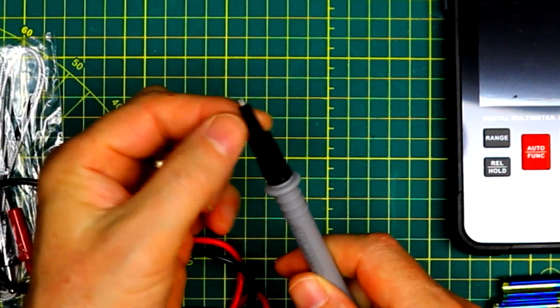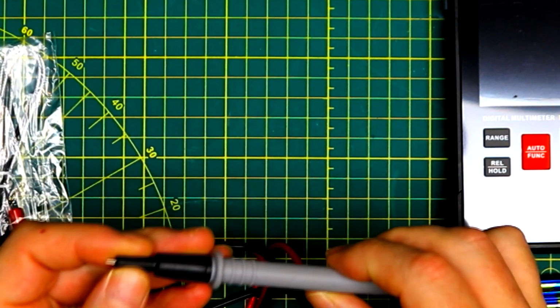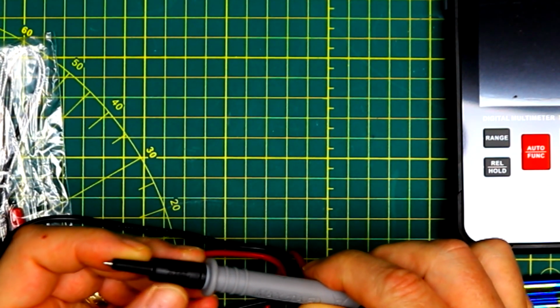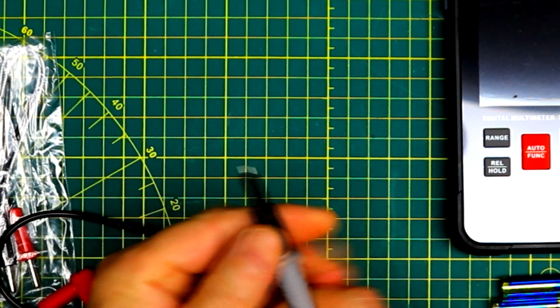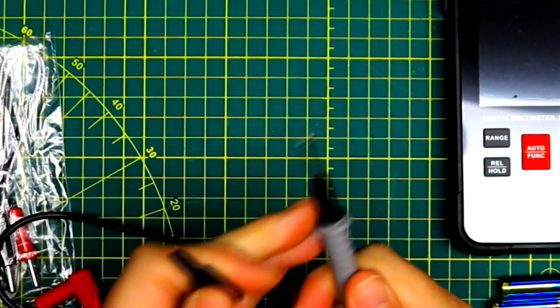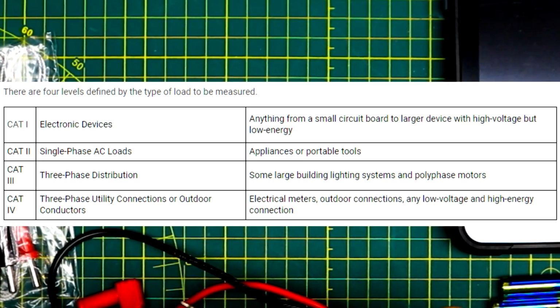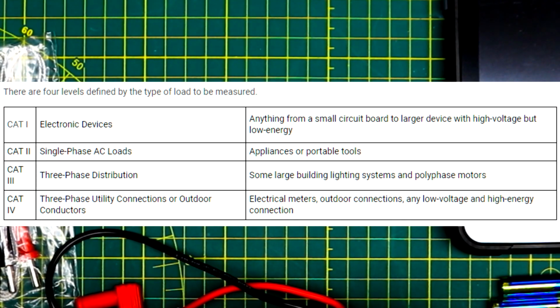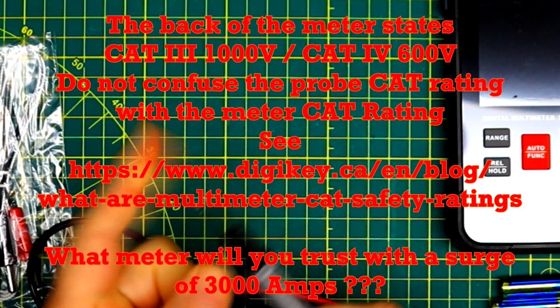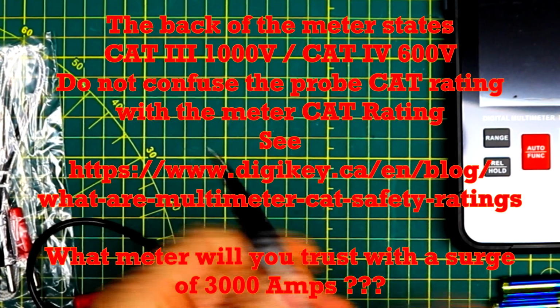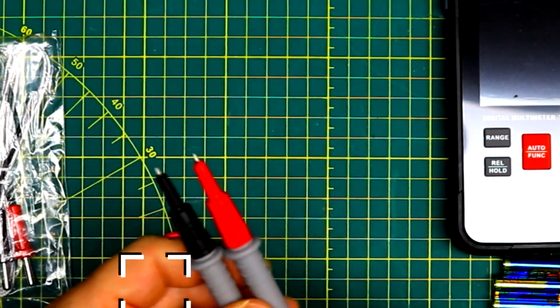On the probe end, they've got covers for the cat rating. When you've got these covers on, there's only the tip exposed, and you can change the cat rating. So that's cat 4 at 600 volts. If you take this off, you actually reduce it to cat 2 at 1000 volts. This is all about category ratings, which I've talked about before — it's about where you can use the meter, not the voltage ranges.